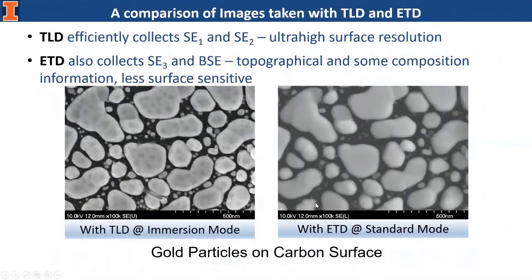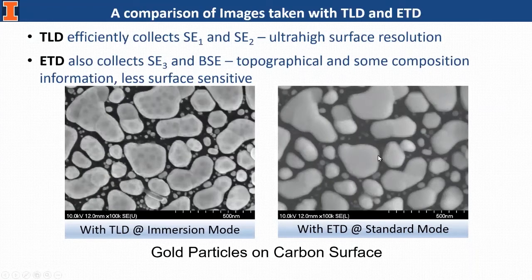Comparing images taken with TLD and ETD on the Hitachi 4800: the TLD image gives more surface detail not seen in the ETD image. The reason is TLD collects SE1 and SE2, while ETD has contributions from SE3 and BSE.